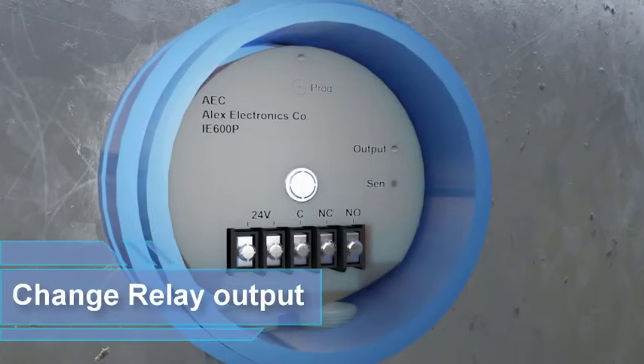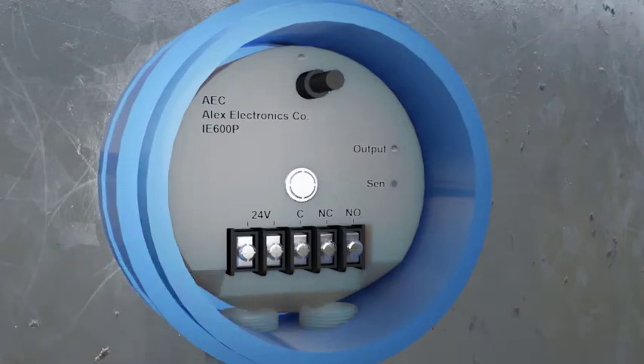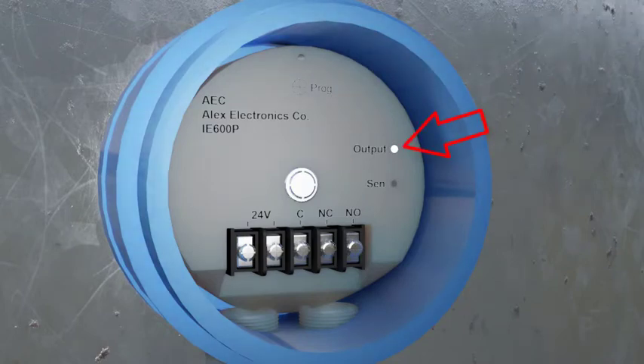To change the relay output from normally open to normally closed or vice versa, point the magnetic pen for one second then remove it. The output LED will be lit for normally closed and dimmed for normally open.